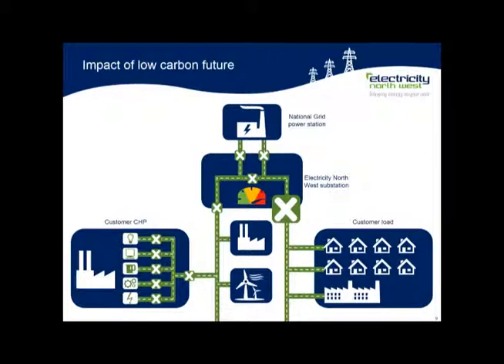The Respond project can help mitigate against this increased fault current and can help defer or avoid the need to replace expensive network equipment. The fault current limiting service could reduce the fault current generated at a customer's premise. When a high fault level is predicted on our network, the equipment at the customer's premises is enabled using new technology being trialled as part of the Respond project. If a network fault then occurs, fault current will flow to the point of fault as before. But the equipment at the customer's premises operates automatically and immediately after the fault is detected. This prevents the customer's equipment from contributing to the fault current on our network.